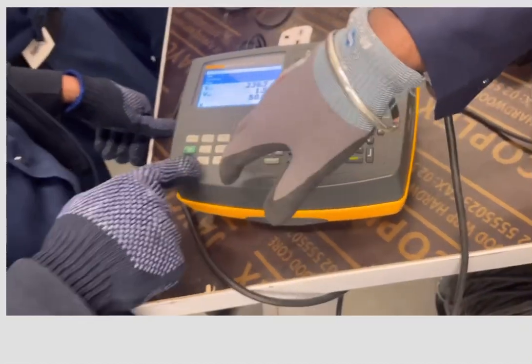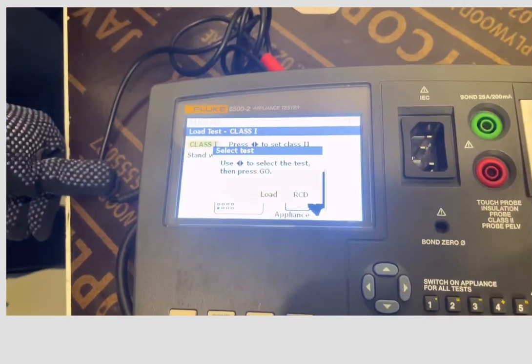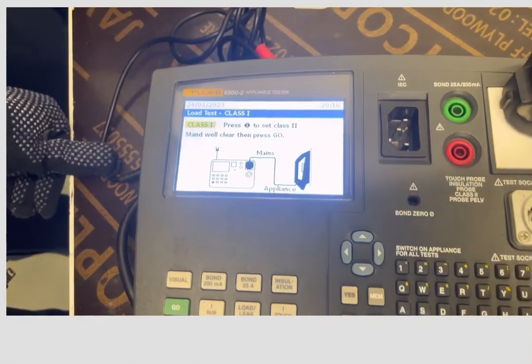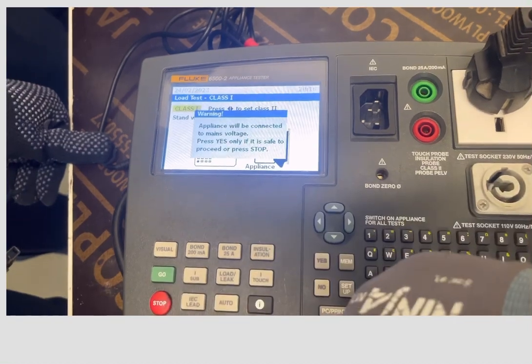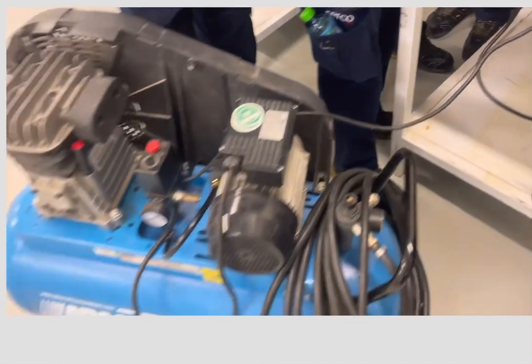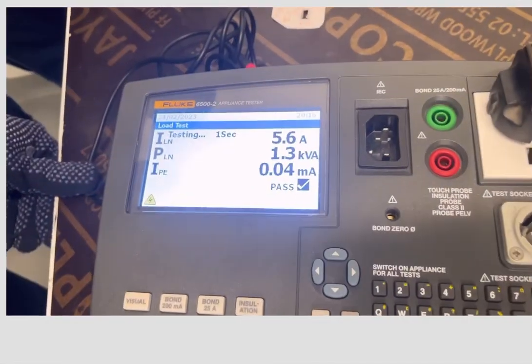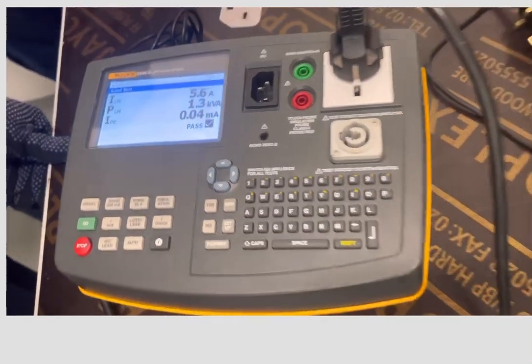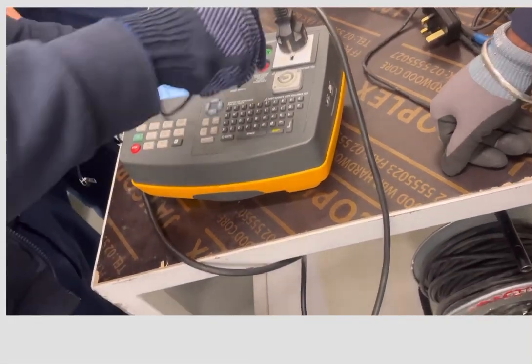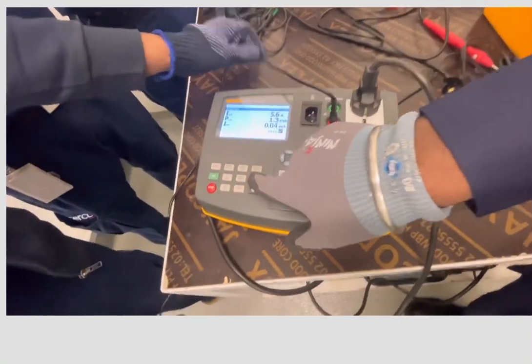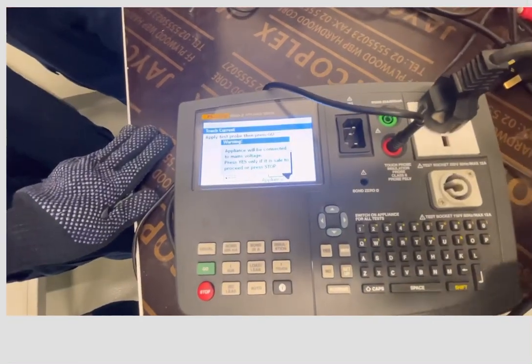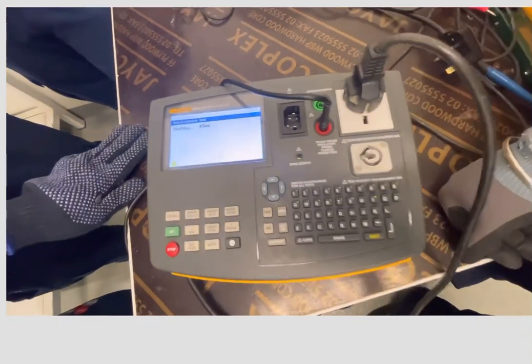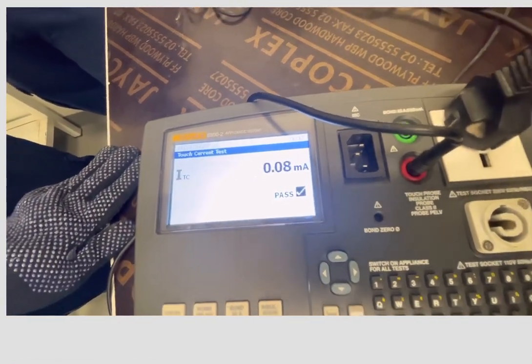We will start from the load leakage test. Select the test and start the load leak test. The value is pass. Now we will go to the touch current test. For the touch current test we will insert the test lead. The value is pass.